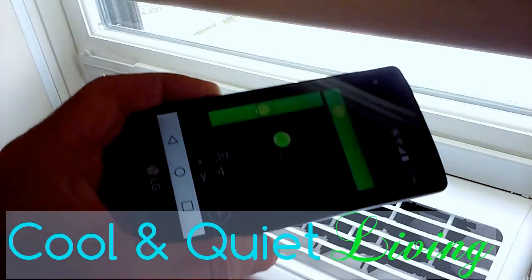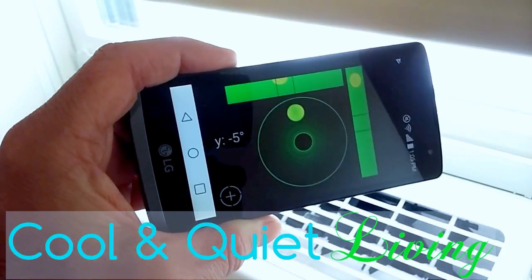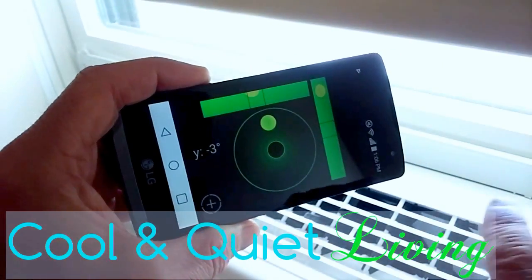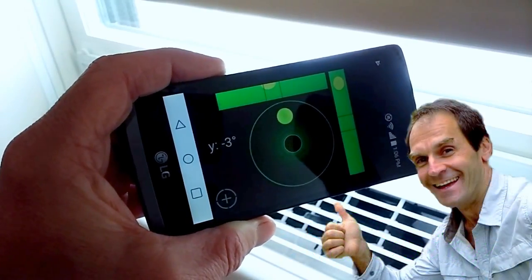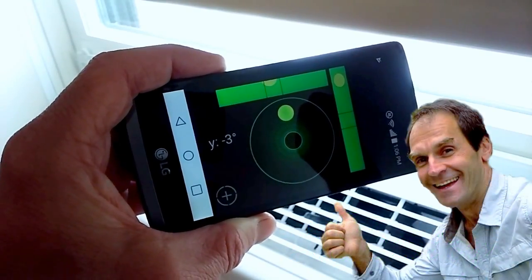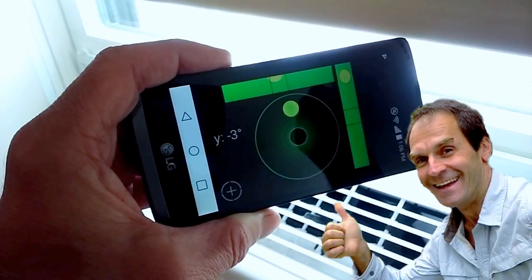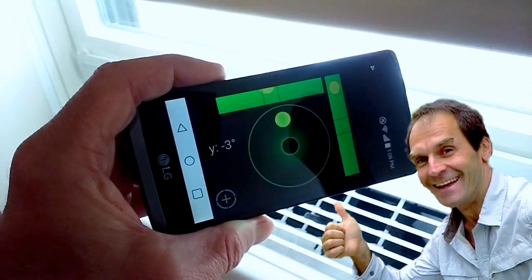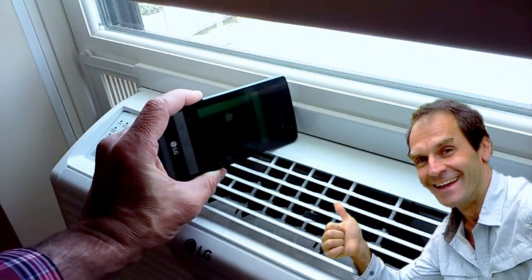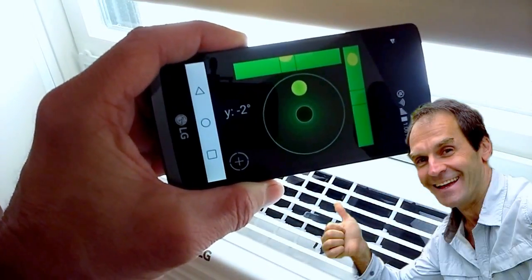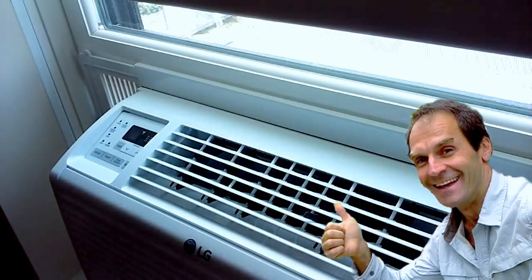Hey friends, Paul here with a tutorial on how to angle your window air conditioner properly — angled back outside so you get proper drainage. For my LG 6000 BTU AC, I've calculated that at 3.62 degrees, and that would be going this way outside. I'm just using a bubble level app here from the Play Store, just as a visual aid.